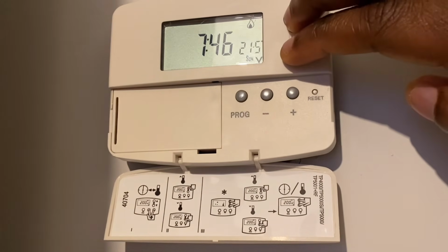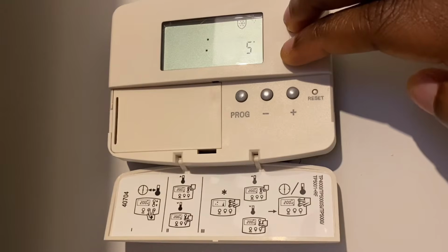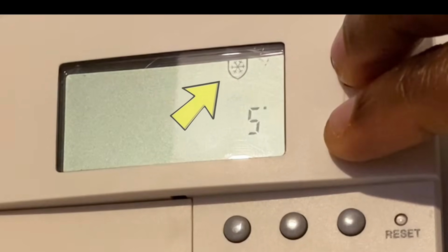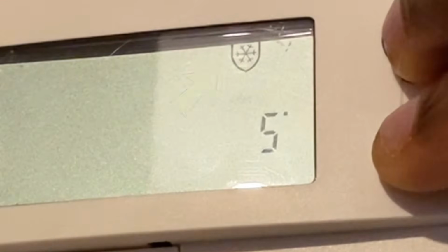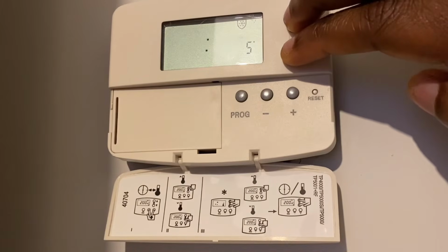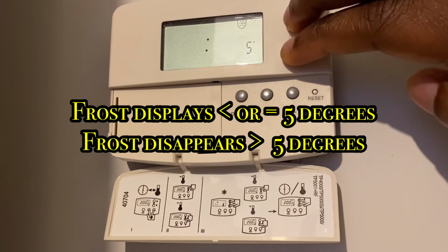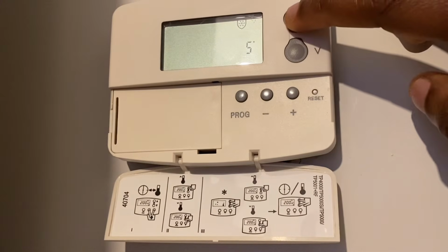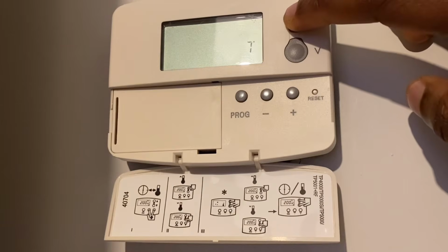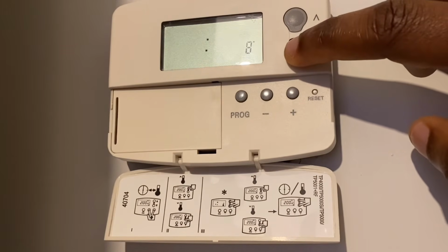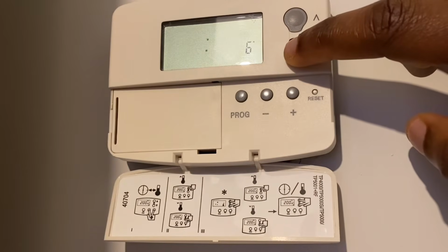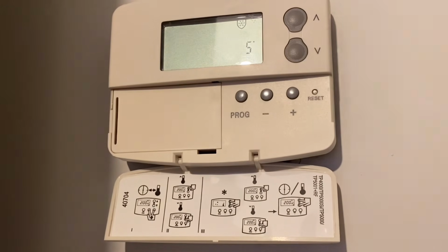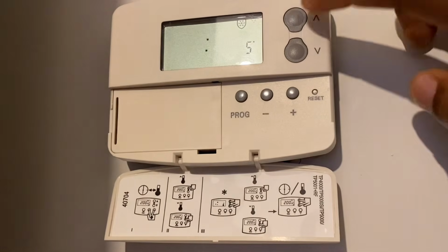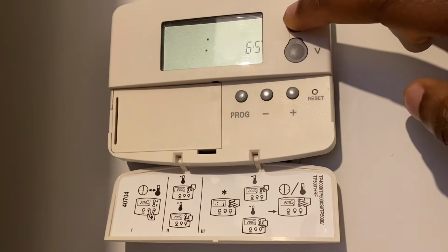So if you press the up and down button here, a frost protection symbol or snowflake in a shield will appear in the display when the selected temperature is equal to or less than the programmed frost protection setting. Suffice to say, equal to or lower than 5 degrees, which is the default setting when you get in the thermostat mode, but as you increase the temperature values, the frost protection symbol or the snowflake shield disappears, and that's because it's greater than 5 degrees, okay?